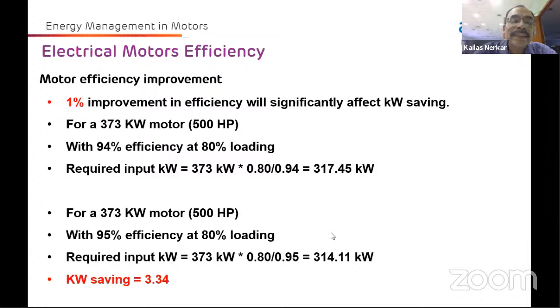That 3.34 kilowatt looks very small for one motor, but on a continuous, yearly basis, you can see how much saving there will be. Calculate 3.34 into 24 hours into roughly 300 days a year, accounting for shutdowns, and you can see how much power saving is possible just by changing the motor's efficiency by 1%. So even though it's a small efficiency gain, try to adopt it.